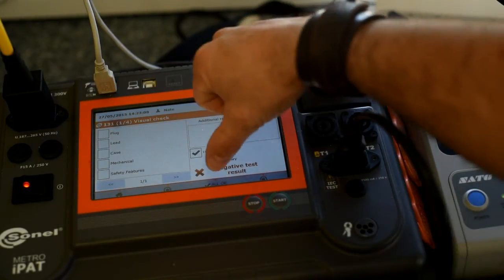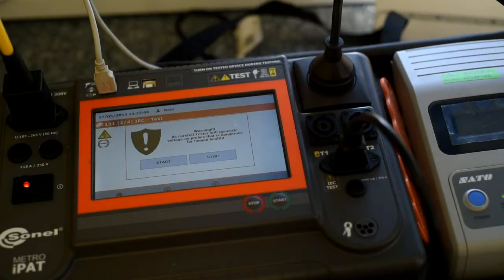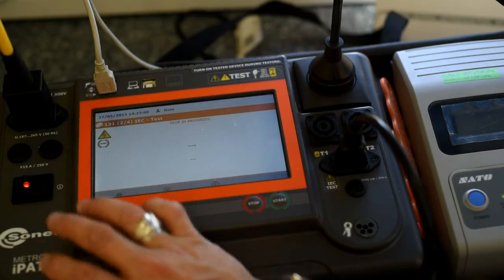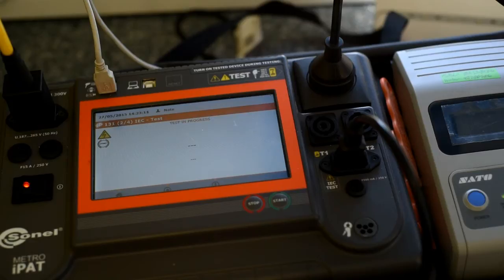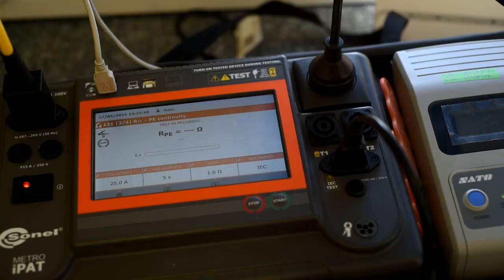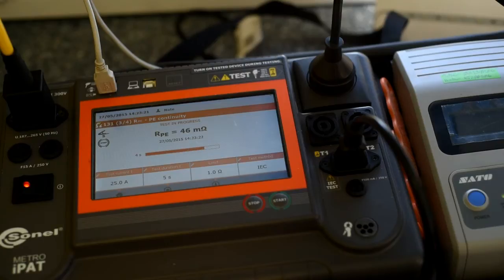Protective earth testing can be classified at two distinct levels. A low current test at 200mA, which is the soft test. And a high current 10 or 25A test, which is our hard test. This falls in line with the current compliance in the ASNZS 3760.